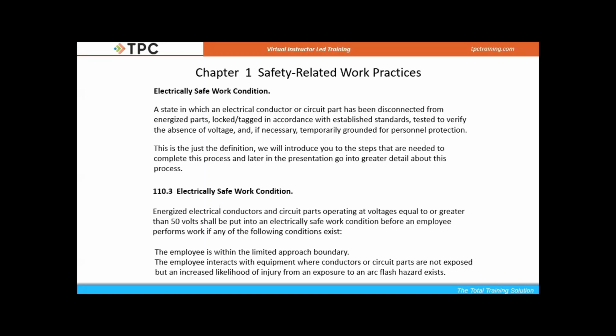So we haven't taken any covers off. We're just going to do something maybe that the manufacturer allows us to do, but there is an increased likelihood of injury from the task that we're about to try to make happen. So for instance, maybe we're going to rack a breaker in and out of switchgear, or we're going to maybe stab on a disconnect onto bus duct. Those are all examples of increased likelihood that an arc flash could occur, and the technical committee for NFPA 70E believes we should establish an electrically safe work condition when we perform those tasks.